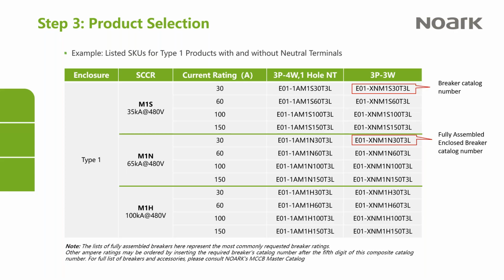Fantastic. Now, we just had a great question come in. This may be a little bit more of an in-depth question, or maybe required a different time, but could you just lay out really quickly the difference between the ACB and the M series circuit breakers, and just a little information on the A series breakers having a higher ampere rating versus the M series limited to 1200? Sure. So molded case breakers and power circuit breakers fall under two different standards, under UL and under CSA.